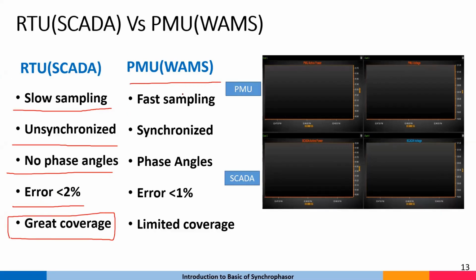Now the PMU is there. What advantage does it have over the conventional SCADA system? It has very fast sampling, providing the same information with phase angle as well as magnitude, at a much higher sampling rate compared to the 2 to 5 second SCADA reporting.